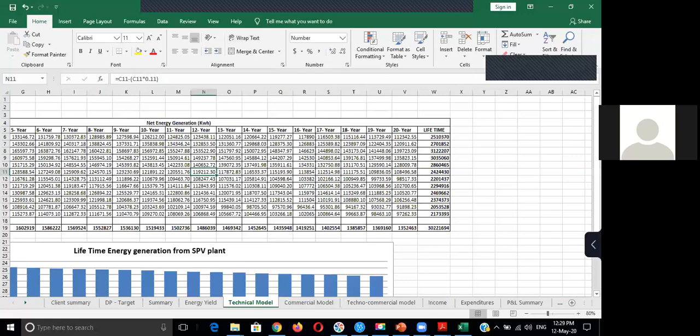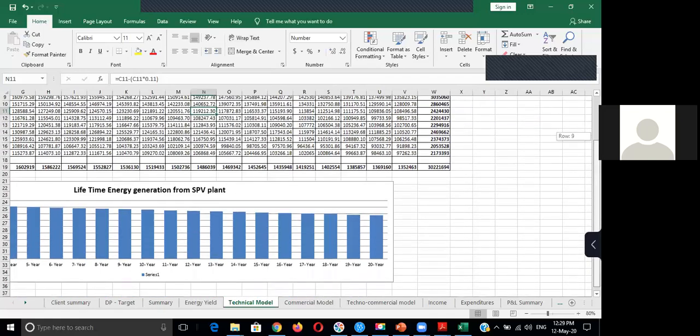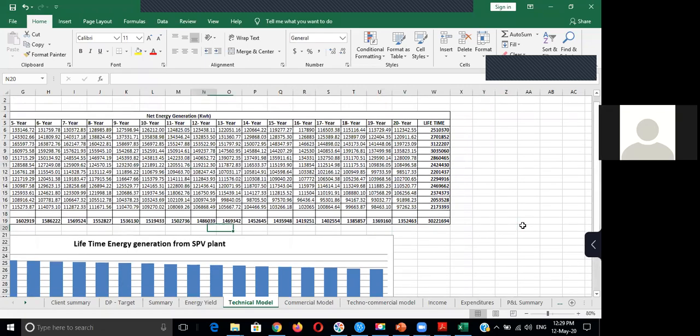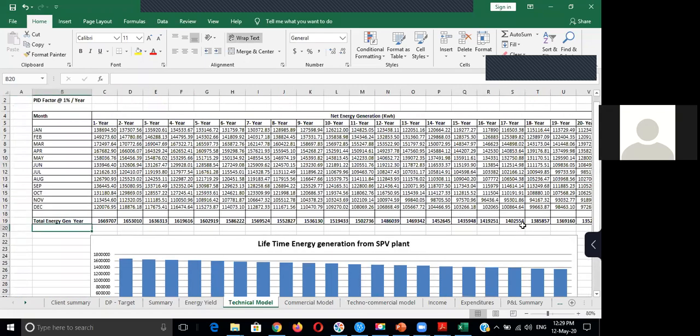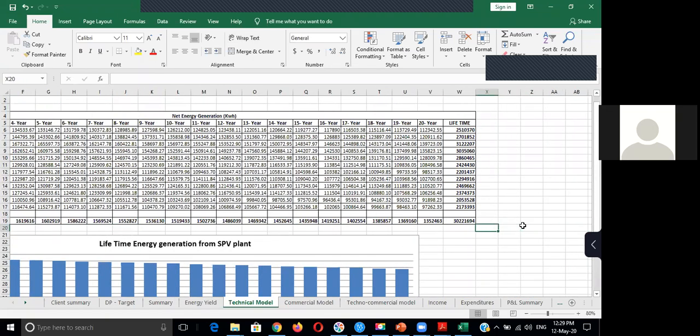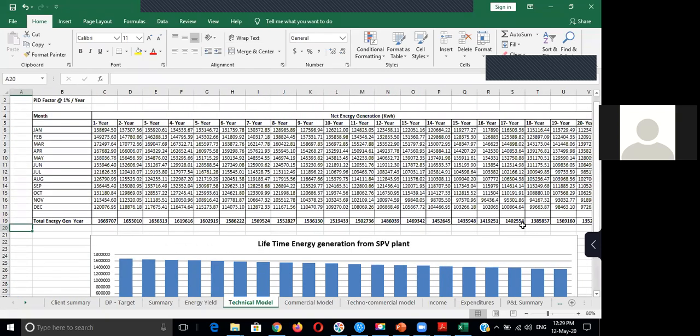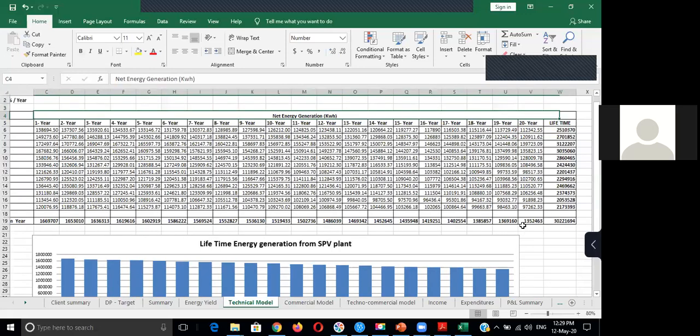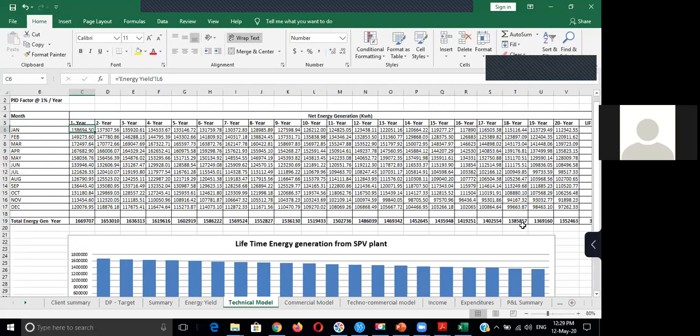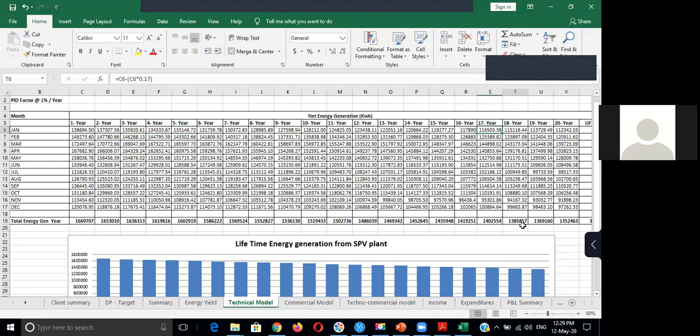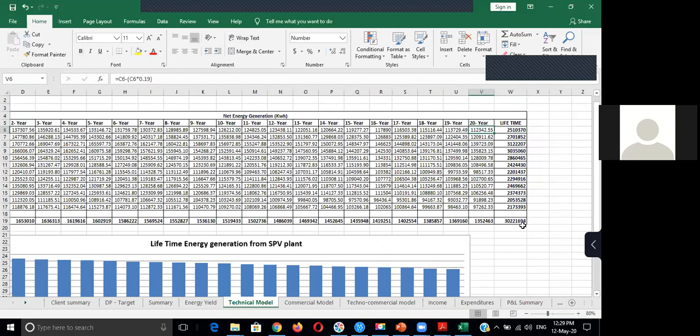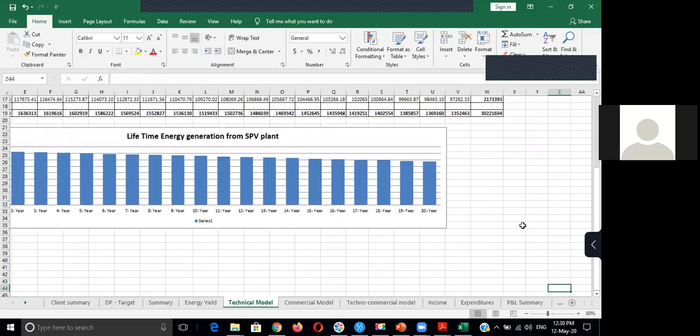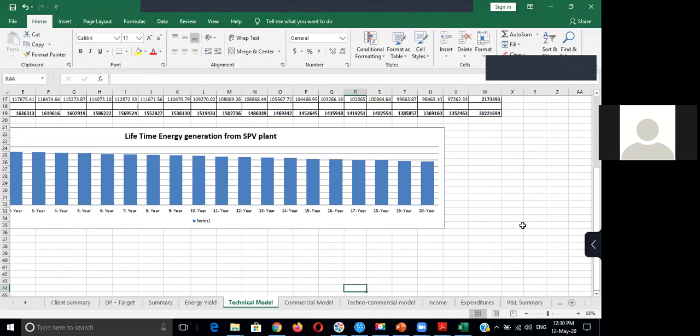So this technical model is actually going to show you what is my generation of the plant which is going to be for the next 20 years. Because any solar plants which you are taking into account for any kind of bigger projects, they will calculate the generation and account its income for the entire 20 years as a business model. So here we have taken into account the PID factor of 1% per year, which means every year I'm going to get a decrease of 1% efficiency from my plant output. As a factor of derating which is nothing but PID - Potential Induced Degradation factor. So if you calculate keep on years and years and years, you can see the kind of decline of its efficiency and what is the total lifetime energy generation which is happening out of the plant. So this is the lifetime energy generation yield study.